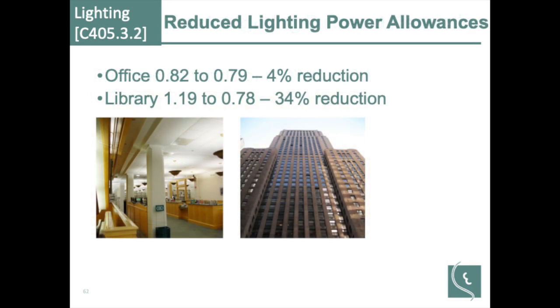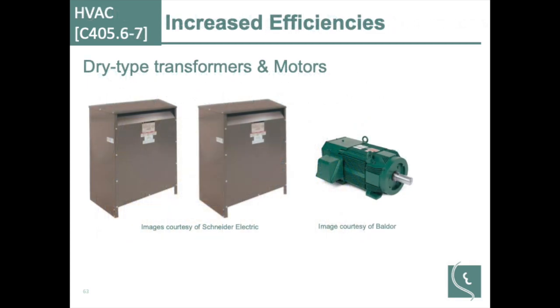Reduced lighting power allowances in office buildings. The office space building area method has been reduced from 0.82 to 0.79, a 4% reduction. Libraries have gone through a much larger, more significant reduction. Again, LED lighting makes it a lot easier, especially when you've got track lighting to highlight rows of books, things like that, that typically in the past kept library lighting power higher. With LED lighting, as it's new technology, it's easier to bring that power density down, so they've incorporated that into the code.